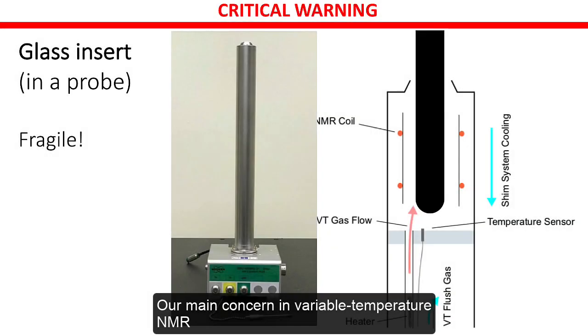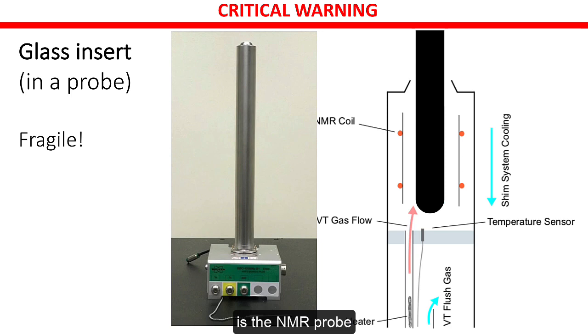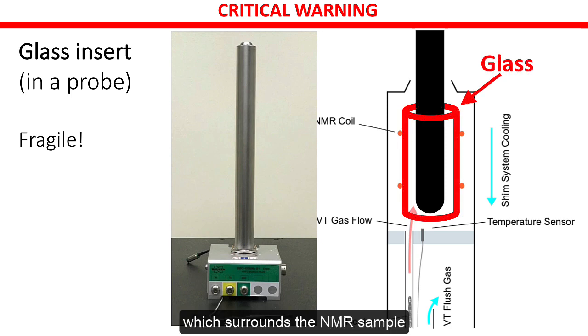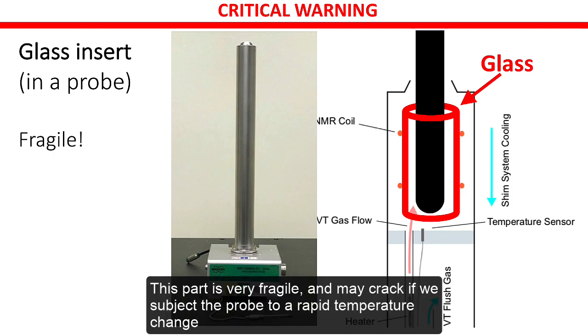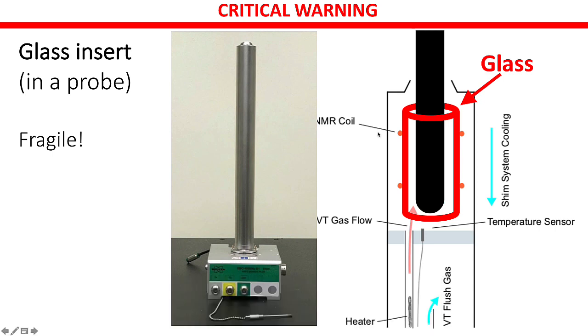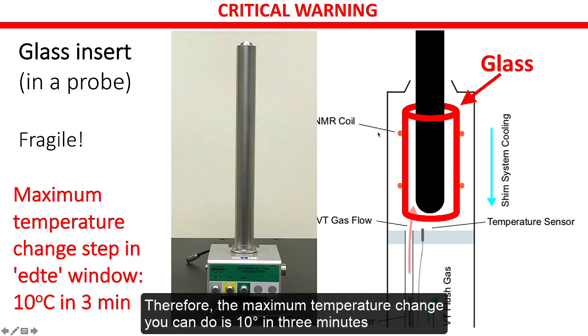Our main concern in variable temperature NMR is the NMR probe. The probe head contains a glass part, which surrounds the NMR sample. This part is very fragile and may crack if we subject the probe to a rapid temperature change. Therefore, the maximum temperature change you can do in the EDTE window is 10 degrees in 3 minutes.